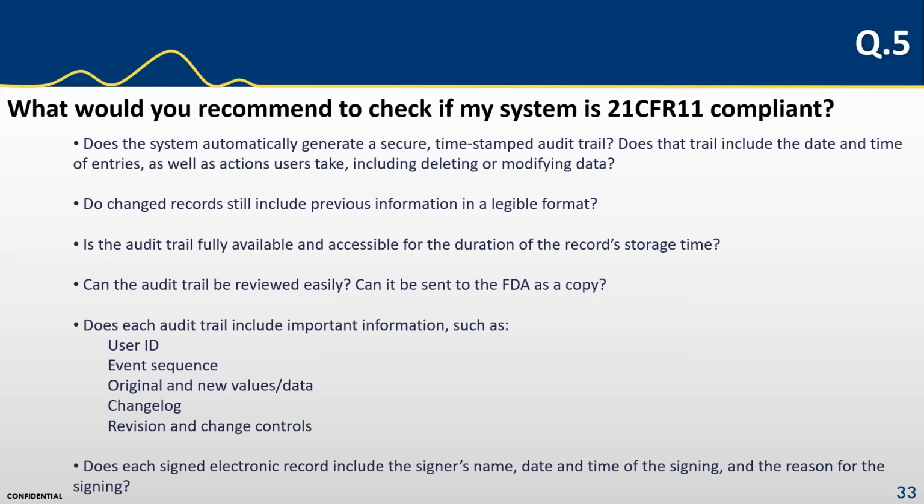Can it be sent to the FDA as a copy? Does each audit trail include important information such as user ID, event sequence, original and new value data, change logs, revision, and change controls? Does each signed electronic record include the signer's name, date, and time of the signing, and the reason for the signing?